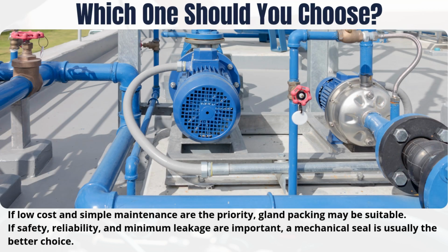Which one should you choose? If low cost and simple maintenance are the priority, gland packing may be suitable. If safety, reliability and minimum leakage are important, a mechanical seal is usually the better choice.